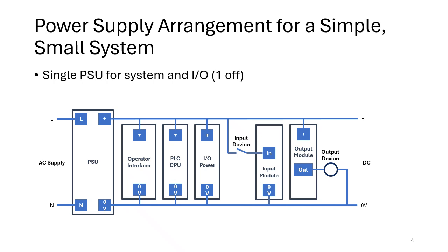So there will be the operator interface, if there is one. There would be the PLC CPU. There would be the I/O power to the actual I/O modules themselves because they need a power supply. There would be the wiring to the input devices, and then there would be the wiring to the output devices through the output modules. So the actual physical wiring might be quite complex, but the overall idea is quite straightforward.